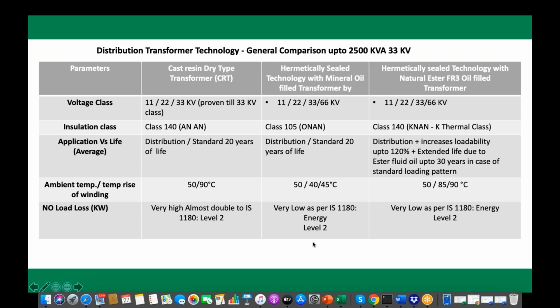And today, we have BIS implemented for efficiencies, which is IS 1180 part 1, which talks about the liquid filled transformer. Meeting those efficiencies with dry type up to certain ratings may be tried, but it becomes enormously costly. It's really very, very costly, and still it's not possible to meet. Because of this technology limitation, we have to allow inferior losses, and that's where we have a limitation. Let's move to the next slide.